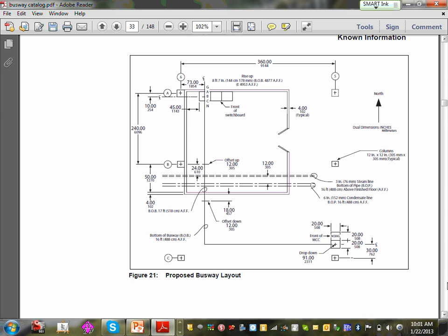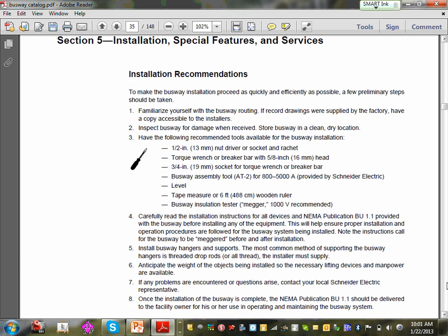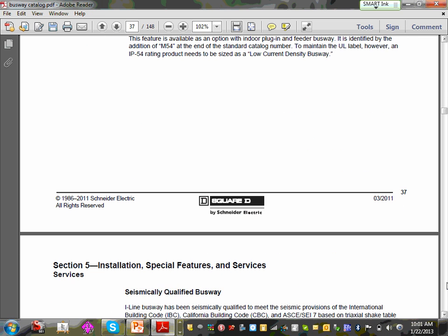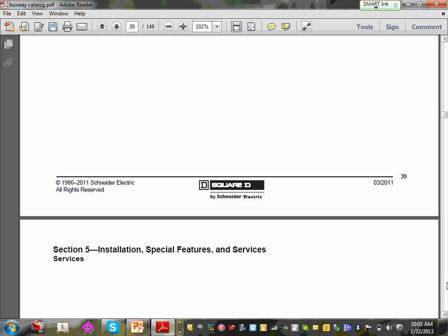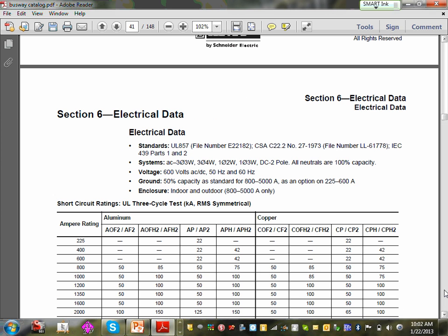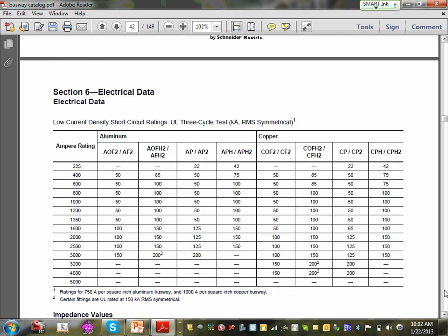So Jerry, when you start with ABC top to bottom at one location, you always end up with ABC? Not necessarily. Well, okay, we're ABC here, right? We're coming up this way. When you turn inside the panel, doesn't your listing require you to have right to left ABC? Or how do you play with it? It's all played with up here in that connection, up in that flange. Okay, I see. So the final destination will be right, top to bottom, left to right, or front to back, ABC.